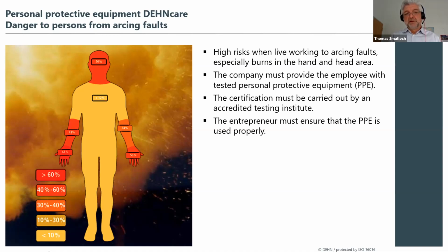Okay, good. So that means to protect the worker from the effects of a fault arc, he should wear personal protective clothes, of course. And the employer of the worker has to make sure that the clothes are tested after certain standards, and they have to make sure that the worker is also using it. That this is not only beside the installation, but he has to make sure that he's really using it.